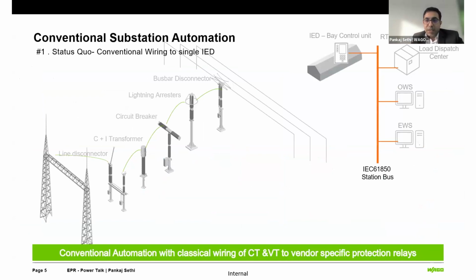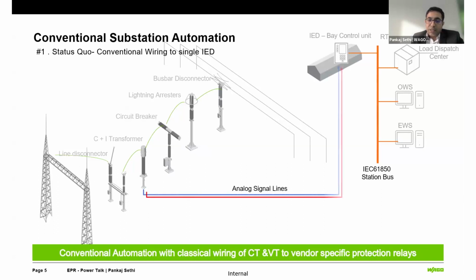What we see here is a standard electrical yard with a control room where numerical relays are present, using the IEC 61850 station bus. The relays protect the entire network and take data from instrumentation transformers in the yard through analog lines - voltage and current signals wired through copper. The breakers are also connected to the IEDs through copper cables for inputs and outputs.